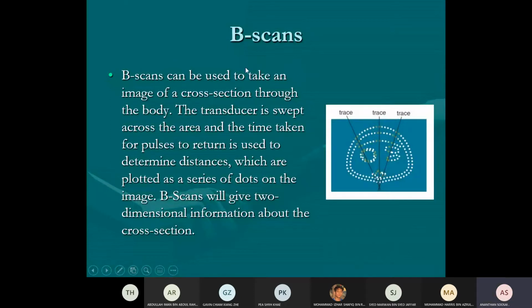Now that's B scan. B scan can be used to take an image of a cross section through the body. The transducer is swept across the area, and the time taken for the pulse to return is used to determine the distance, which is plotted as a series of dots on the image. A series of A scan images is combined to form a 2D view. B scan will give two-dimensional information about the cross section. So B scan is better than A scan because it can give two-dimensional information. The layers.